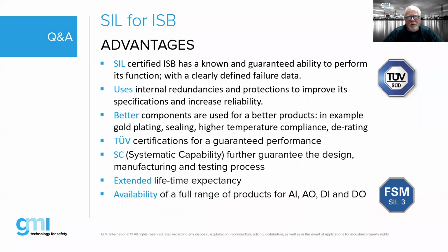The reliability is known, and generally speaking, because in order to get a SIL rating on, say, for example, an intrinsically safe barrier, you have to go back through each and every component, traceability, and then you have to find out the failure rates of all of those components. You have to make those calculations. And so when you put that in the field, you have a pretty good understanding that this product is going to survive for an extended period of time. That's basically the advantage of using SIL. Safety for safety. All right.